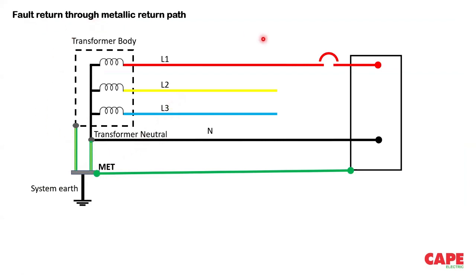Now, I'm showing you a TN system. A TN system consists of a transformer, on the left side. On the right side, you can see, for example, an equipment, and then there is an OCPD, a protective device. What is important is the green wire, which is nothing but the metallic fault return path. Metallic fault return path means that in case of a fault, the fault current from the equipment returns back to the source through the metallic fault return path. This resistance is probably 100 milliohm, or sometimes even 2, 3, 5, 10 milliohm in a very large installation, or in a residential situation probably 300 milliohm, 500 milliohm, things like that. It is very, very less.